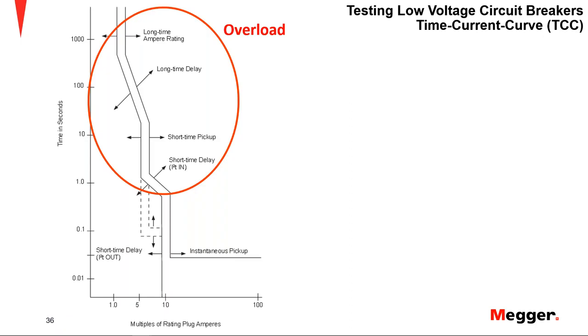Right? So again, this allows those motor faults to clear before deciding to trip the circuit, or before the circuit breaker trips. And then we have the long time on the upper section right here. The purpose of this setting is, in the same sense, to allow a time-based delay to elapse before tripping for low-level current faults. Examples of these types of overcurrents would be overloading of a power transformer or a large motor for a few minutes. Again, just giving time for those low-level current faults to clear before the circuit breaker trips.